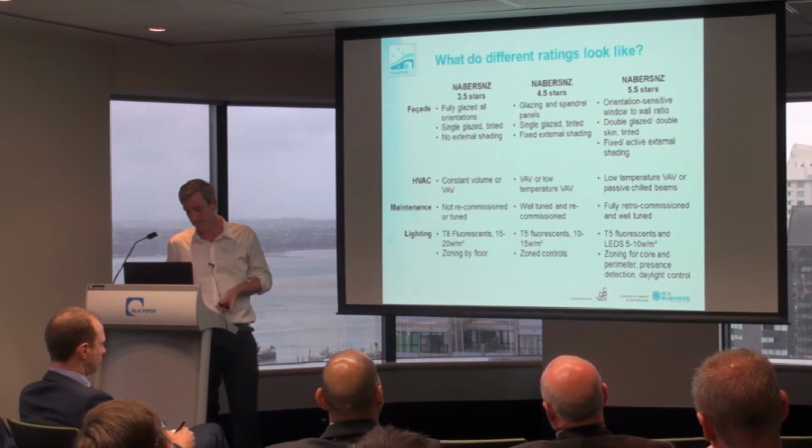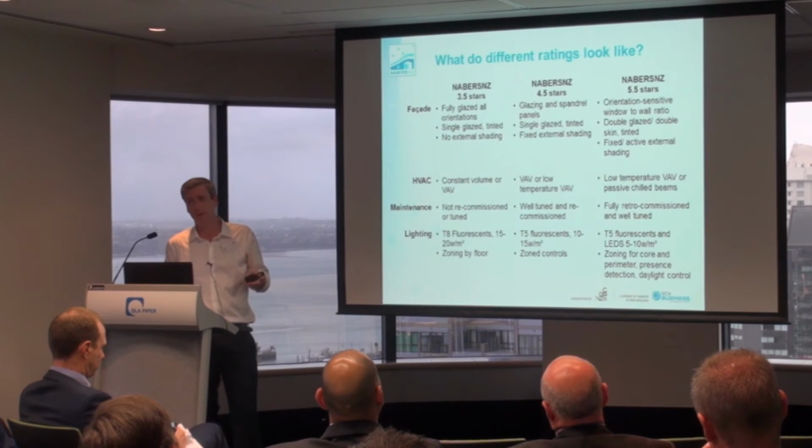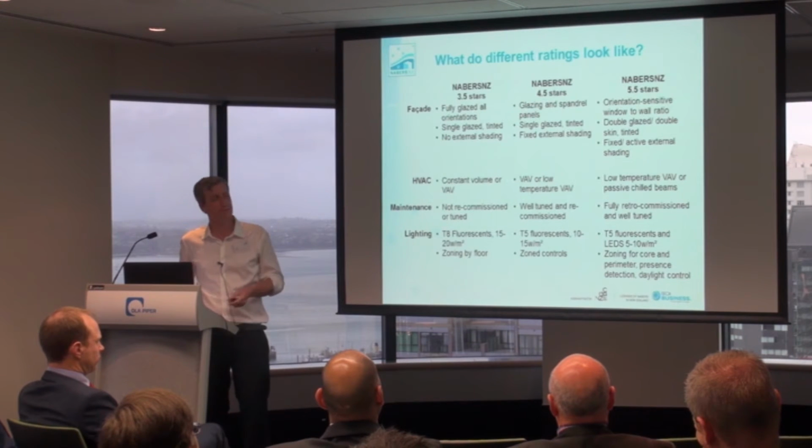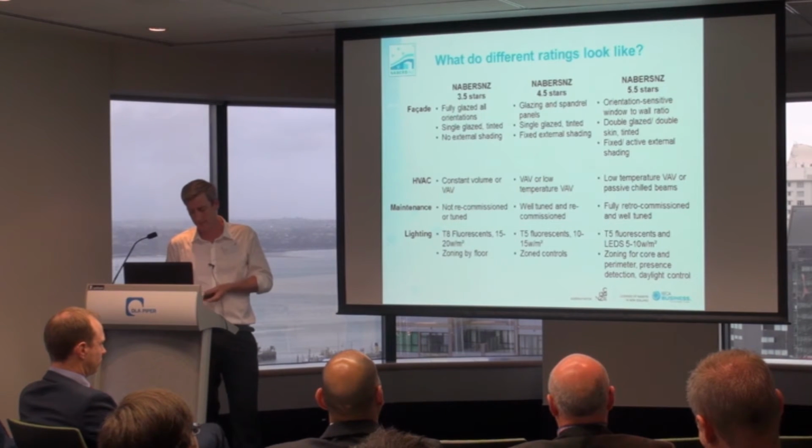newer buildings can. So in regards to HVAC, 3.5 is constant volume or VAV systems, 4.5 is VAV or low temperature VAV systems, 5.5 is low temperature VAV or passive chilled beam. So once again, a huge difference in technology within those buildings to get the ratings.